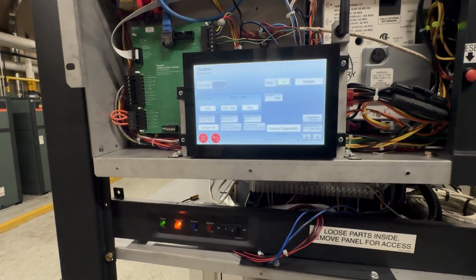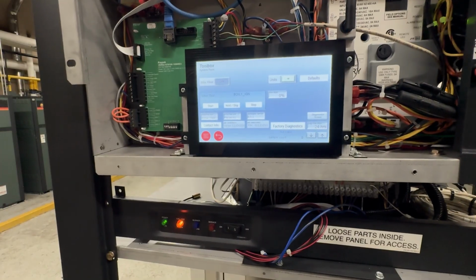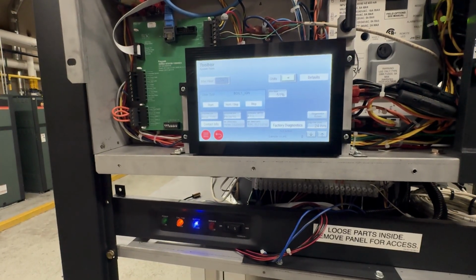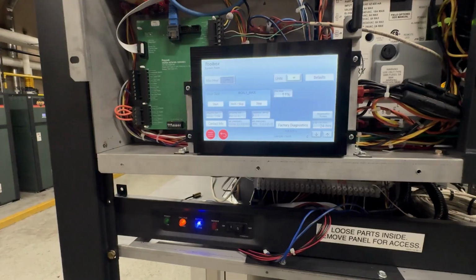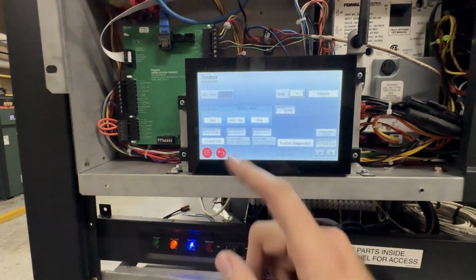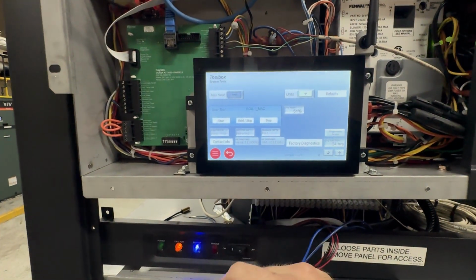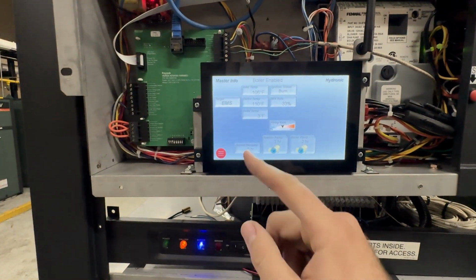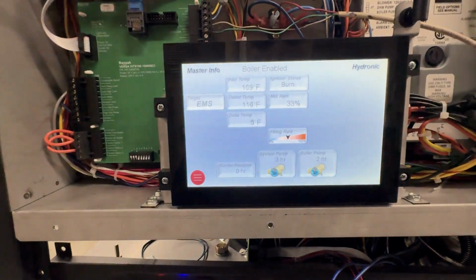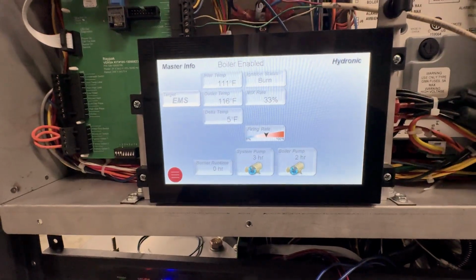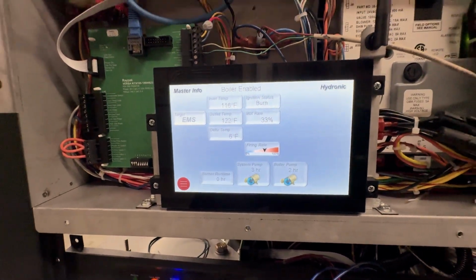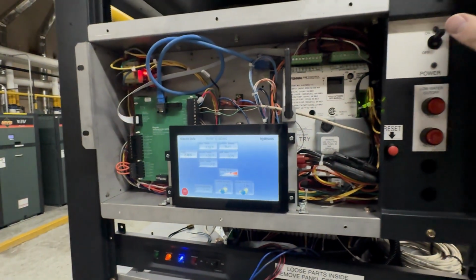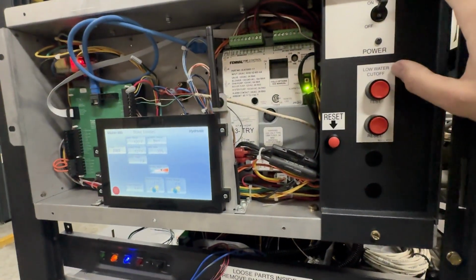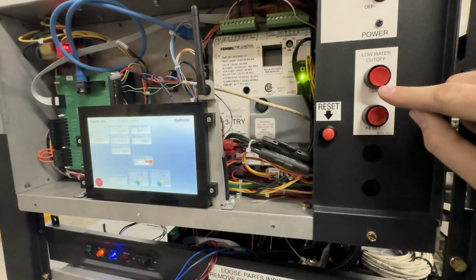There's the gas valve. There's the burner. Now it's going to run up to max temperature. Ignition status burn. Inlet temp is 111, outlet's 116. So one of the first safeties we're going to test, over here on these rate packs, they have the low water cutoff. We're going to hold down the test button.